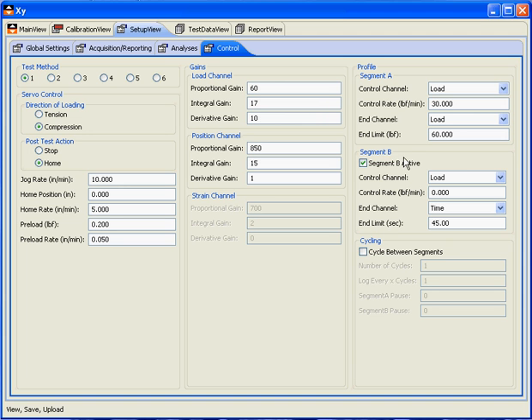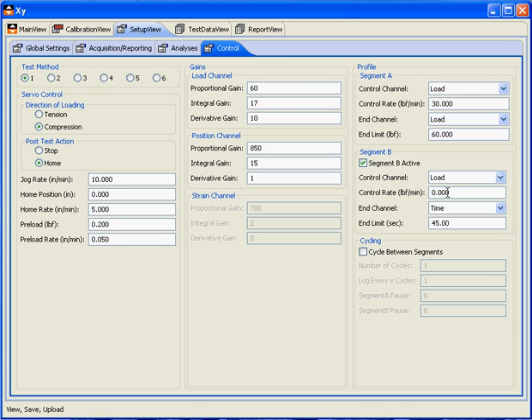Segment B is basically the holding segment where we want to hold that load for a certain period of time. For this, we set the load, the control channel to load, the control rate to zero, and then the end amount to be time, with the end limit being 45 seconds.